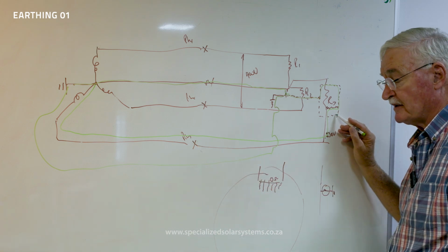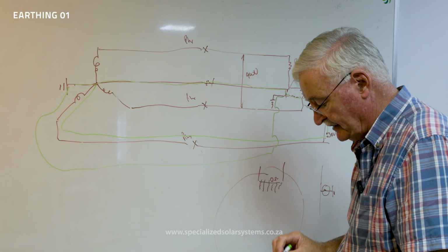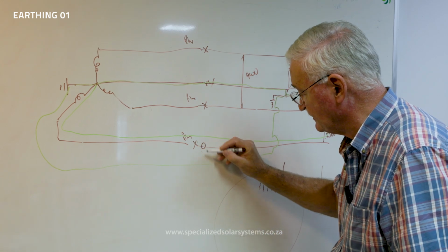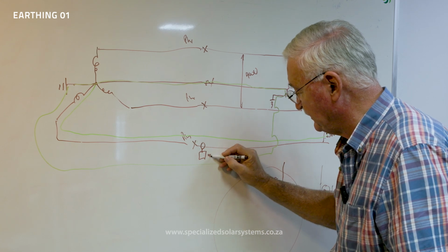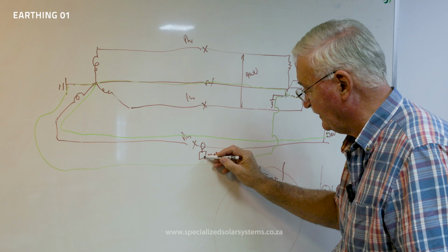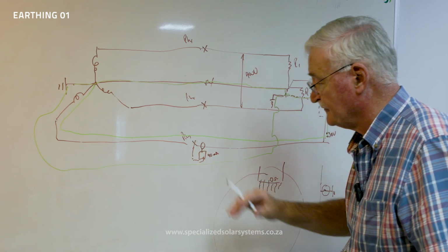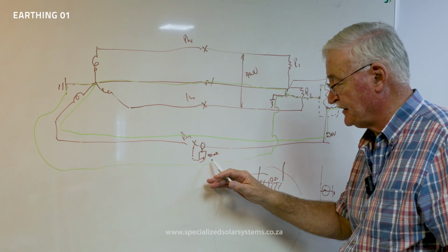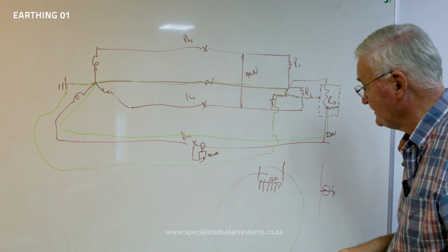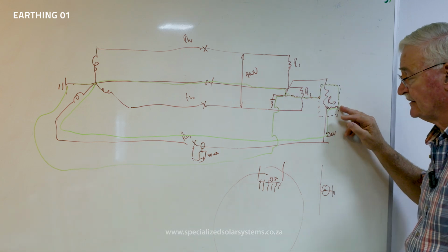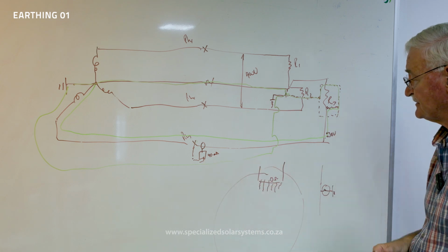But if that leakage is quite small, it won't pick it up. So what they do domestically, they put another little relay, a gadget, in here. They put a current transformer in here, and they've got another circuit here that's very sensitive and can pick up a difference of 40 milliamps. And that is connected to that breaker. So this little device, which is an earth leakage relay, will pick up currents as small as 40 milliamps to isolate that breaker. If you didn't have this earthing, that relay wouldn't have picked it up, and that casing would have stayed alive.